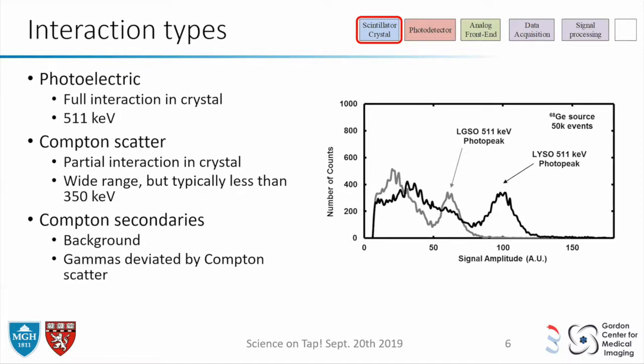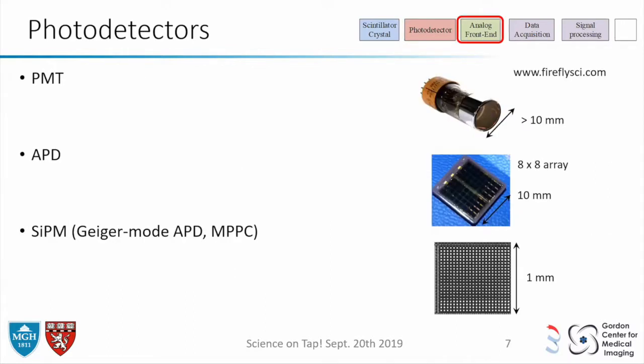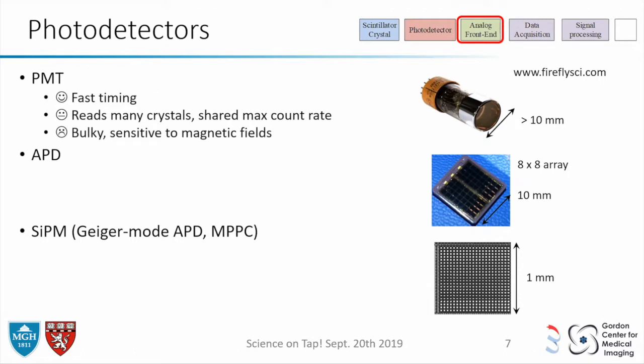After the crystal, we have the photodetector. Historically there were many kinds. One is the PMT, which is still in use today. The advantage is it's pretty fast and can read many crystals, though sharing means reduced count rate performance. The disadvantage is it's bulky and sensitive to magnetic fields, which means you can't use it in an MRI.